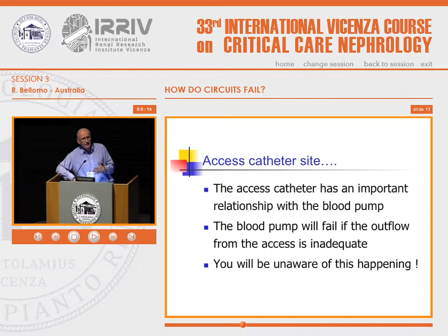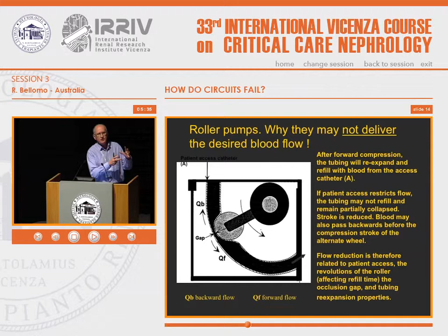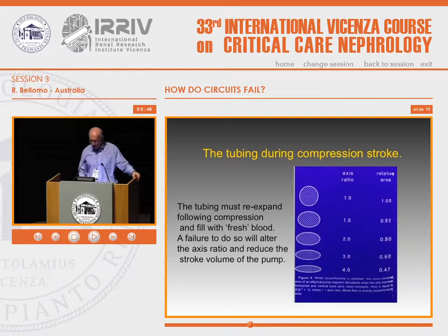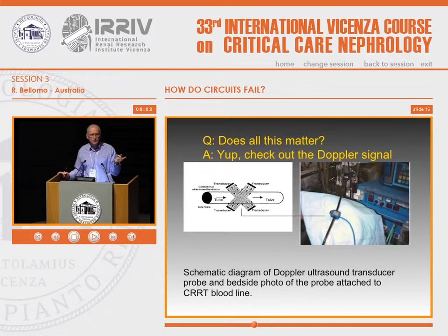And of course, then the catheter will interact with the pump technology. And the pump technology that we have used until now and continue to use is based on a roller system, where you're squashing the tubing that is surrounding the pump. You create, during the rotation, a squash of the tube, which generates a suck pressure to refill the tubing and allows the blood to move forward or outside of the circulation with a progressive squash and refilling of the tubing. Now again, this relationship between catheter and pump matters a great deal, because the machines that you have will measure the rotations of the pump, but they're not actually measuring the actual blood flow that might or might not be taking place while the pump rotates.